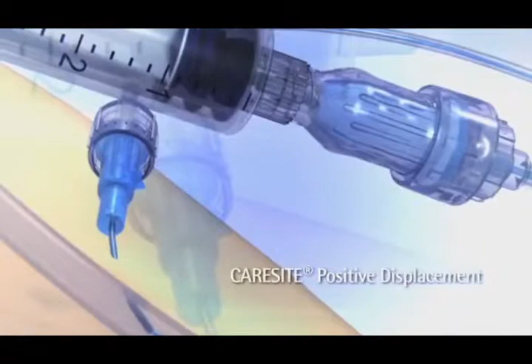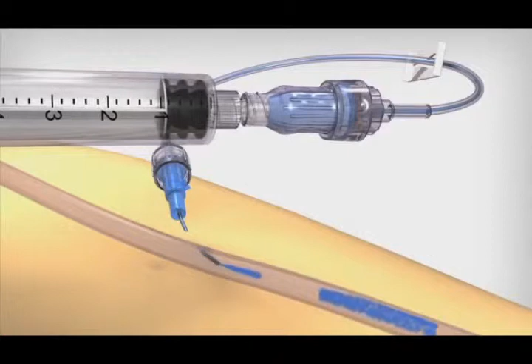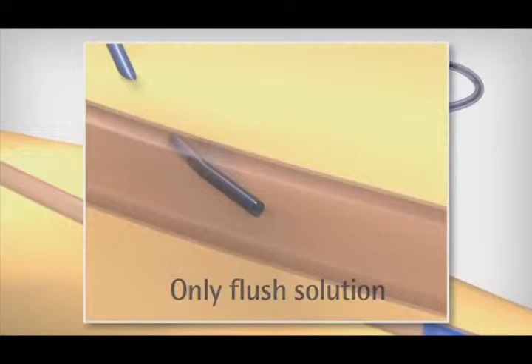The positive displacement feature automatically pushes a small volume of fluid through the catheter when a Luer syringe is disconnected from the Caresite Luer access device. Let's watch that again in slow motion. Positive displacement prevents blood from coming back into the catheter lumen, which may cause occlusions. This is a one-time burst of fluid, 0.03 milliliter, not a continuous pressure. As a result, the catheter contains only flush solution.